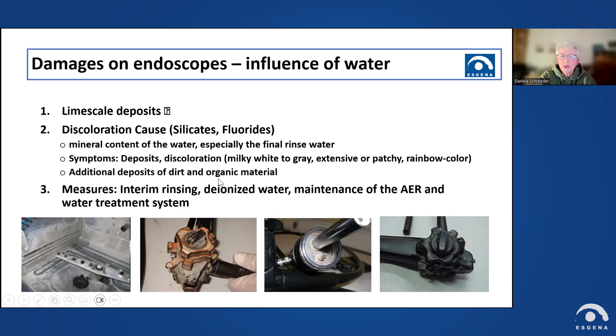Doses of chemicals, so again, another one with a reaction on the surfaces of the endoscope: the concentration, the contact time, or undissolved crystals, especially, for example, when using peracetic acid, which is provided as a powder and needs to be prepared carefully by stirring everything around. It's time consuming, I know. And if you then have some crystals remaining on the floor of the sink, and you put the endoscope in directly, it will have direct contact with these crystals, and this is a high concentration. So we can find this peeling.